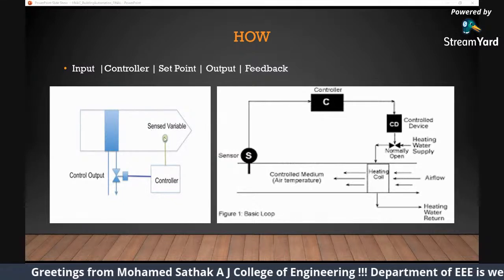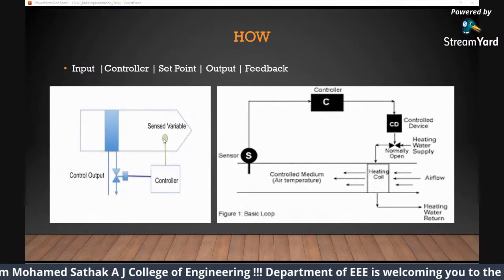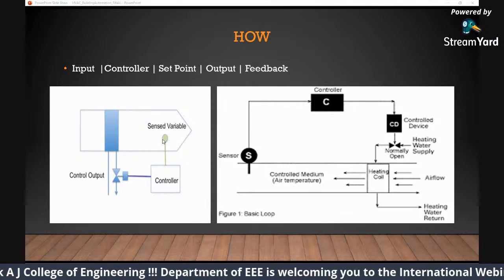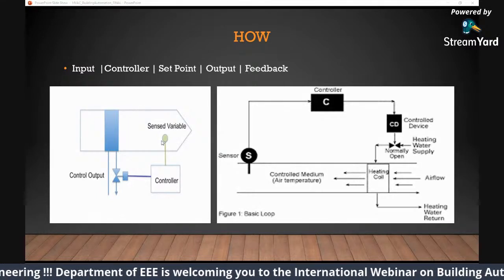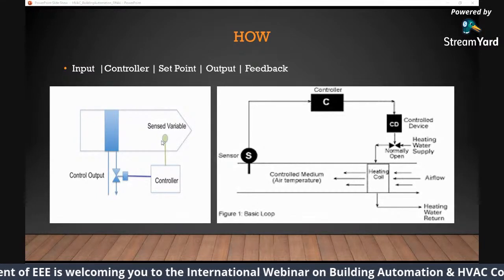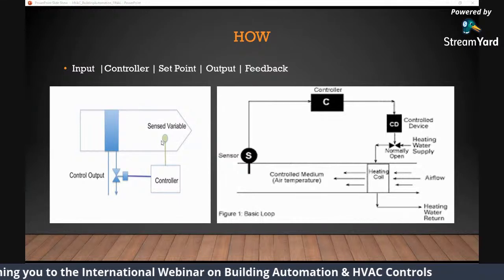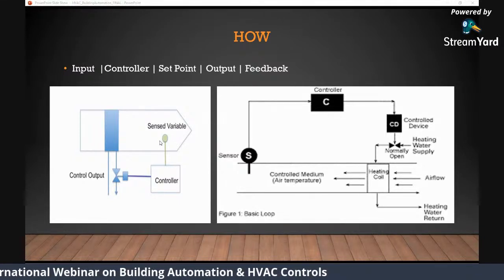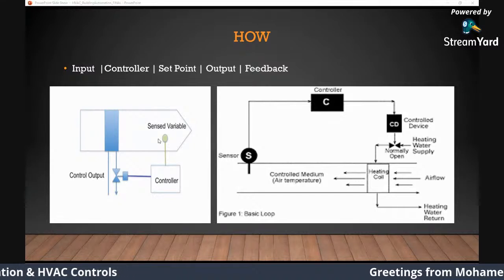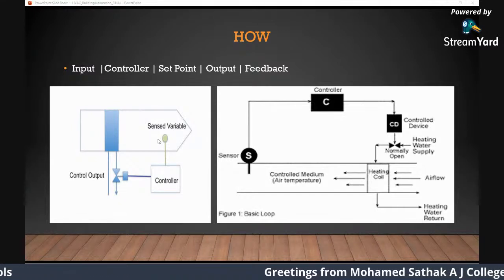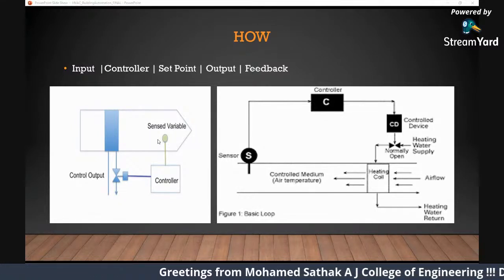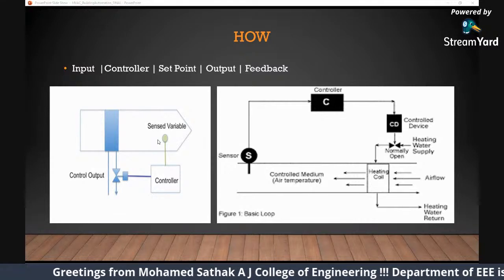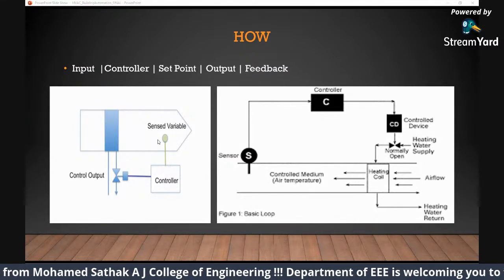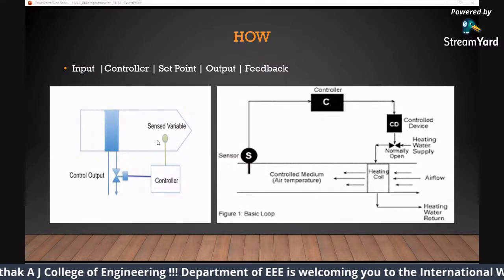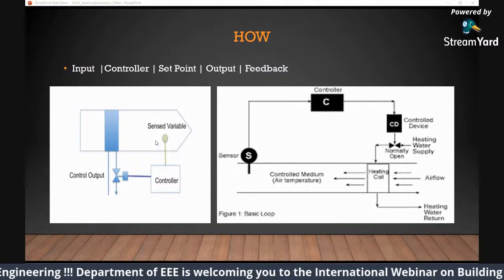Control output, control sensed variables. These are the three aspects to control something in your HVAC. I've been mentioning temperature because that's how I can relate it to your day-to-day life. But there are so many aspects in the HVAC field. We control the pressure in a boiler, the pressure in a chiller. We control the flow. We control the level in a cooling tower. Sometimes there is humidity in the room, and there is viscosity, and there are so many parameters we control and monitor in an HVAC system.